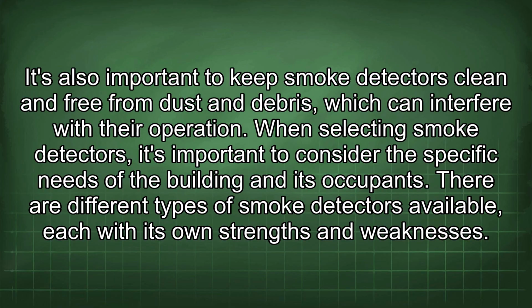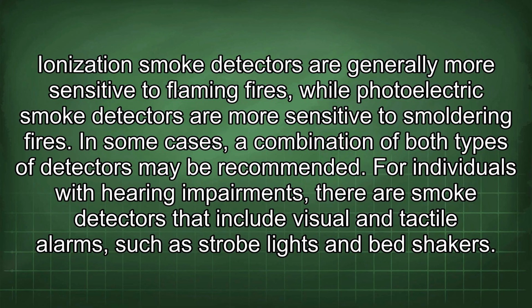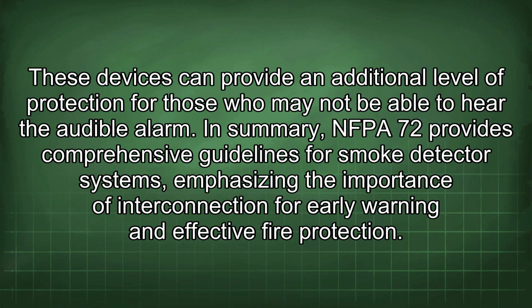When selecting smoke detectors, it's important to consider the specific needs of the building and its occupants. There are different types of smoke detectors available, each with its own strengths and weaknesses. Ionization smoke detectors are generally more sensitive to flaming fires, while photoelectric smoke detectors are more sensitive to smoldering fires. In some cases, a combination of both types of detectors may be recommended. For individuals with hearing impairments, there are smoke detectors that include visual and tactile alarms such as strobe lights and bed shakers. These devices can provide an additional level of protection for those who may not be able to hear the audible alarm.